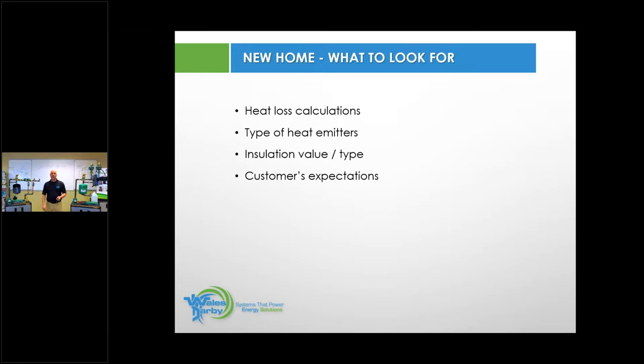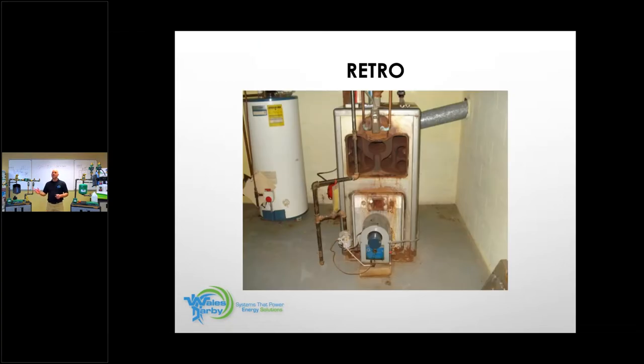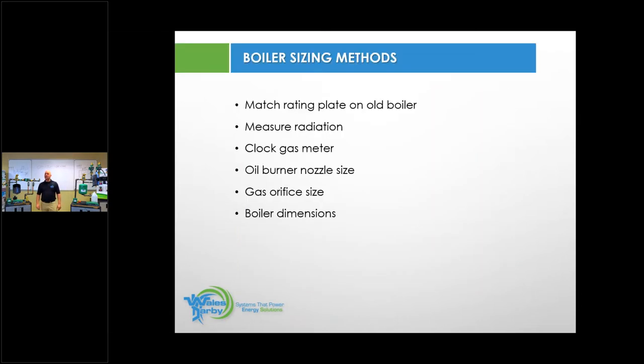Very important to know that and understand it. Then we're going to get into this retrofit job. And retrofit, that's probably the majority of what a lot of guys are doing today. A lot of companies are doing. So there's a bunch of different ways to size the boiler, right? We're going to match the rating plate on the old boiler. And that works, sure. You have the exact same size boiler that you had in there for 30 years.